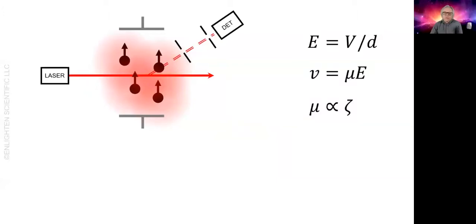Let's look at electrophoretic light scattering. If we shine a laser beam through a sample of particles, each particle will scatter the light and create a Doppler shift dependent on the velocity of that particle. It's like a police radar speed trap. And if you have millions of particles, then you have millions of Doppler shifts all contributing to the intensity of the scattered light.